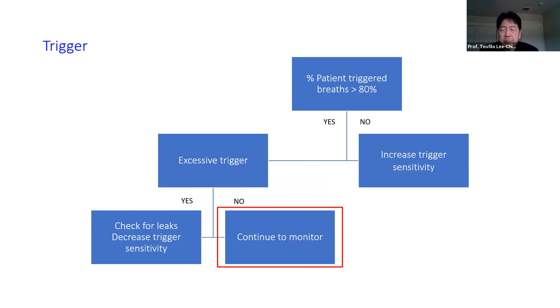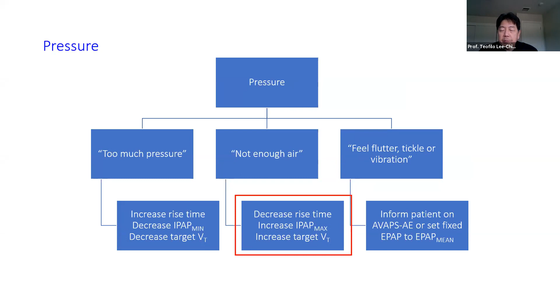Finally, with pressure, if the patient complains of too much pressure, you have some options: increasing the rise time, decreasing the IPAP minimum, or decreasing your target tidal volume. When there's not enough air, then you can do the opposite. Decrease the rise time, increase your IPAP maximum, or increase your target tidal volume.